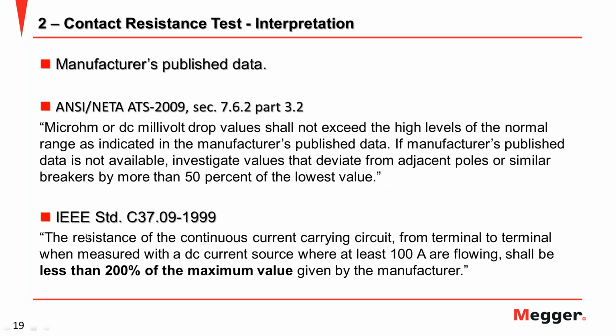And other standards like IEEE C37 state the value should be less than 200% of the maximum value given by the manufacturer. But still, this standard needs the reference value from the manufacturer. And then you can estimate that as long as the value is less than 200%, the contact is still fine, still okay. But the goal is you need to make sure the contact resistance is as low as possible.